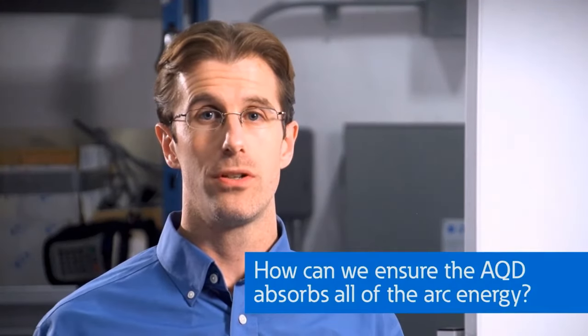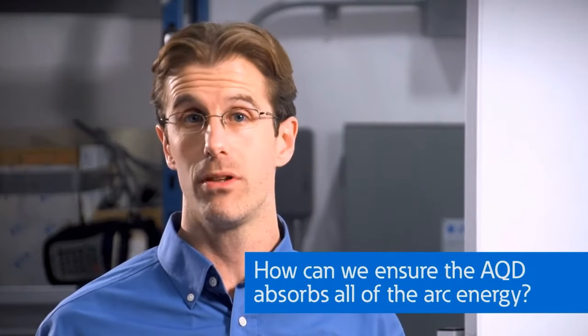But by now you're probably asking yourself, how can I be sure that this is always going to be the path of lowest impedance? Because we're actually introducing some impedance by creating a secondary arcing fault. Wouldn't it be possible to introduce too much impedance so the current wouldn't all flow into the arc quenching device and would still feed the unintended arcing fault? Fortunately, the answer is pretty simple.